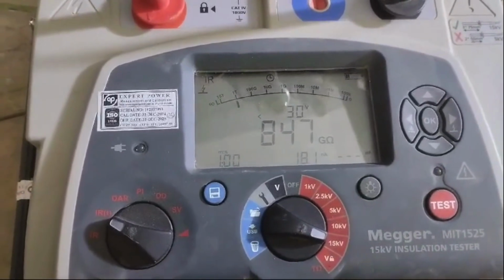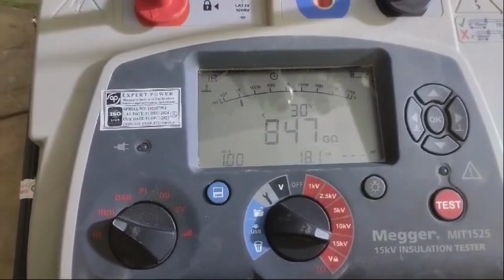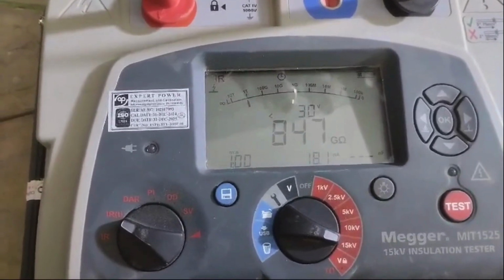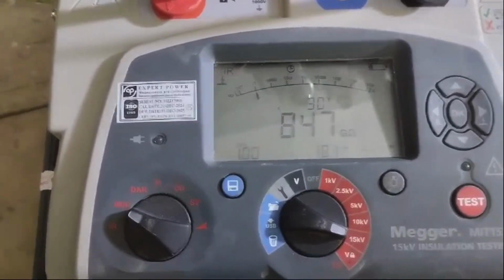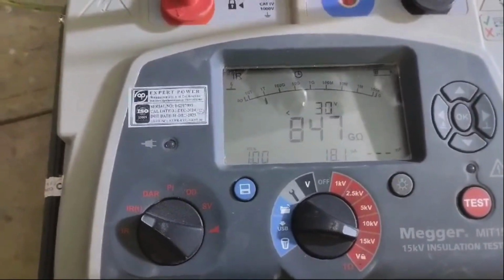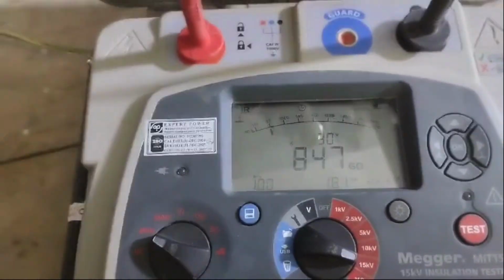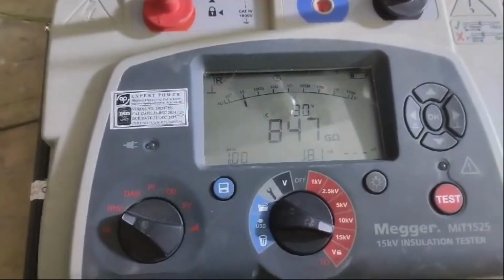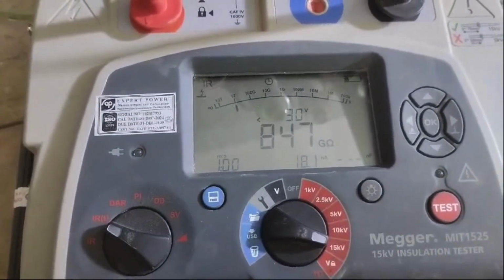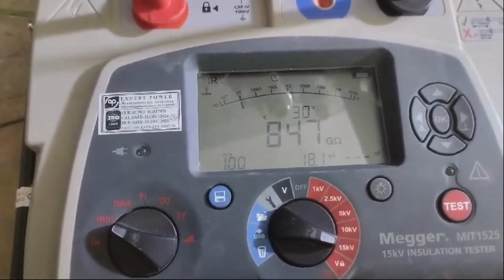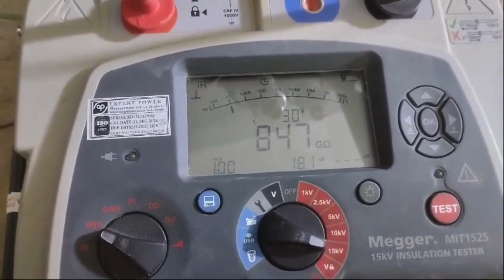We will keep injecting for up to 1 minute to see the insulation resistance value of this cable. Now you can see here the insulation resistance of this cable is 847 giga ohm, which is too much. So we can say that our cable is in healthy condition.